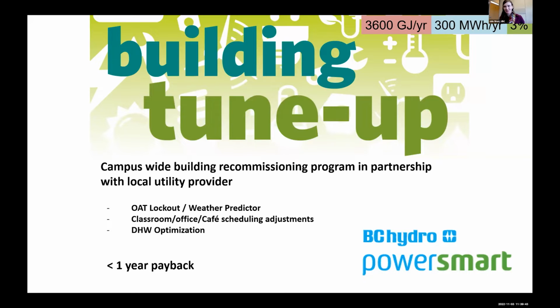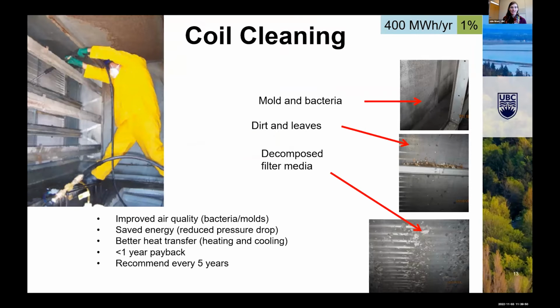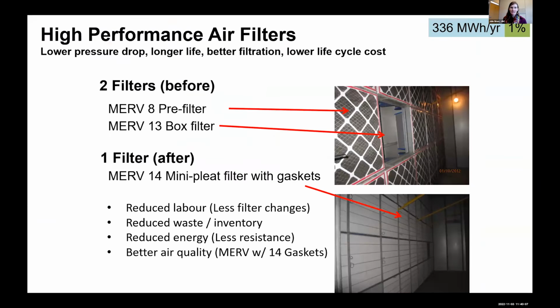I've got a lot of info here, so I'm going to move through these pretty quickly. The next thing that we looked at on campus, and particularly in this building, was coil cleaning. There hadn't been a lot of maintenance done on coil cleaning or filter changing in our buildings. When we had somebody come in and look at them, we found a lot of dirt and debris, mold and bacteria. So we put together a coil cleaning program as well as a filter changing program. Both of these allowed us to reduce energy consumption through reduced static pressure on campus, and have better air quality. We also changed the filters on campus from MERV 8 and MERV 13 to MERV 14 mini-pleat, which allowed us to reduce maintenance on campus as well.